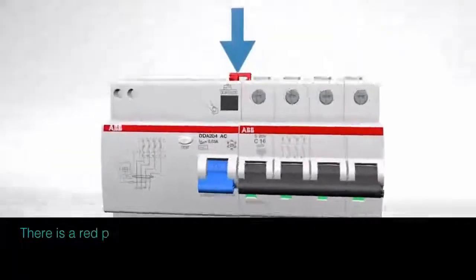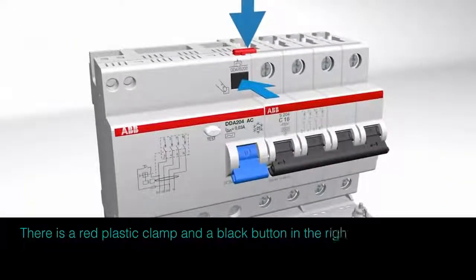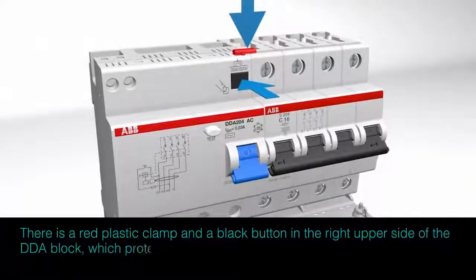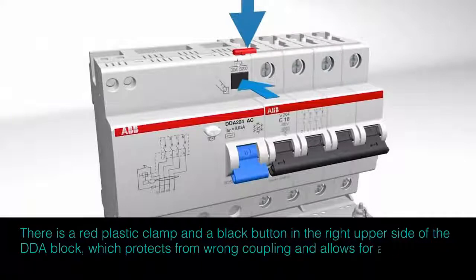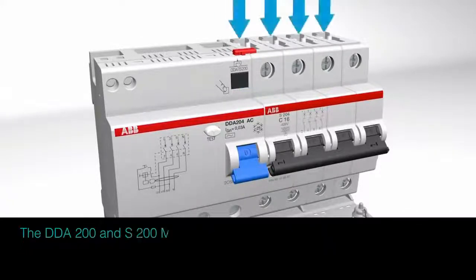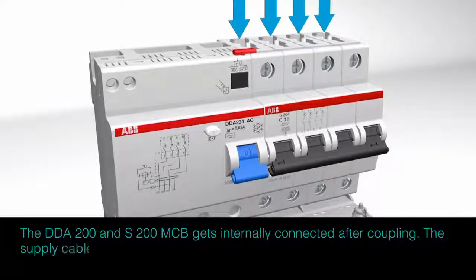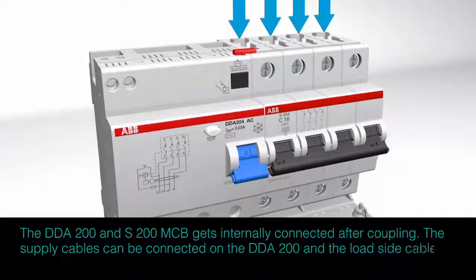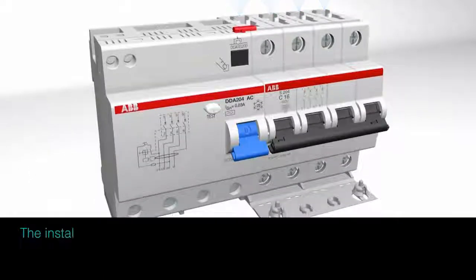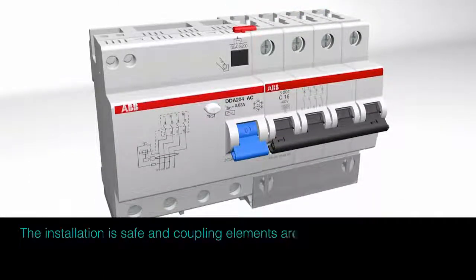There is a red plastic clamp and a black button in the right upper side of the DDA block, which protects from wrong coupling and allows for a quicker assembly. The DDA 200 and S200 MCB gets internally connected after coupling. The supply cables can be connected on the DDA 200 and the load side cable can be connected on the MCB. The installation is safe and coupling elements are not losable.